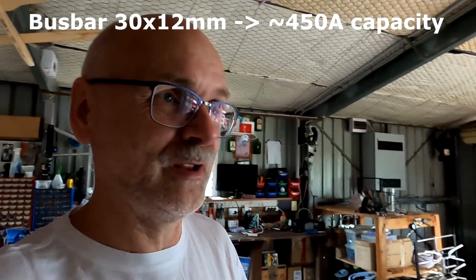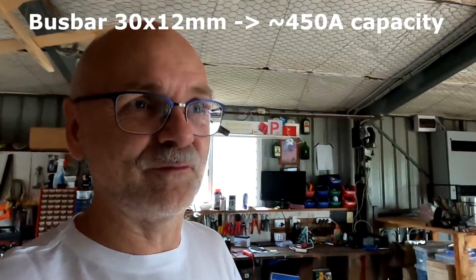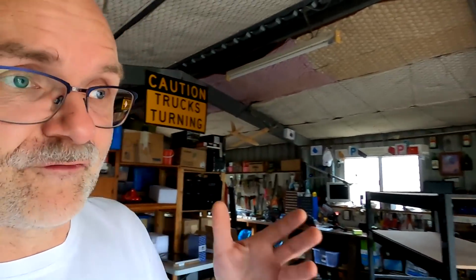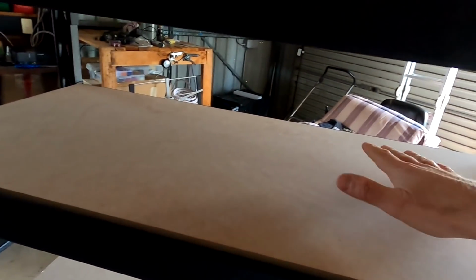I'm still undecided what kind of size I want. I'd probably go for a 30 by 10 or 30 by 12 millimeter, which gives me around 400 amps of carrying capacity. This should be around $350 or something for a 4 meter length. They cut this into pieces, whatever I like, and I get the offcut as well, which we'll then need for our system up here to connect all the switch gear together.